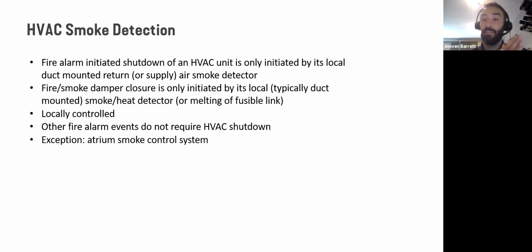theoretically, it should stop the flow of smoke and the unit can continue to run, continue serving the rest of the building. You know, imagine a large DOAS unit serving multiple floors of the building. You don't necessarily need to shut down the entire unit. So long as you can contain the smoke, you can continue to serve other floors. Crucially important in something like a hospital, you don't want to be shutting down your operating room air handlers because there's some smoke detected in the pantry on the other side of the building.